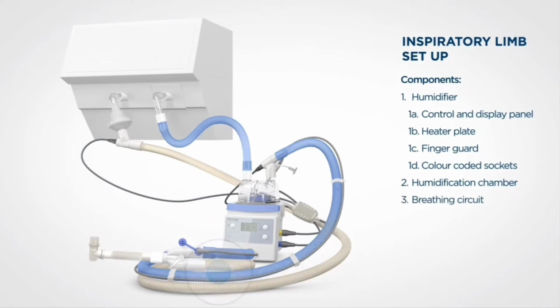This is the breathing circuit. It connects the ventilator or other flow source to the chamber and carries humidified gas to the patient. In the case of dual limb ventilation, it also carries the expired gas back to the ventilator. In this setup, you can see the breathing circuit attached to a catheter mount that would be affixed to an endotracheal or ET tube. In this setup, you can also see an expiratory filter. Filters may be added to either the inspiratory or expiratory limb.